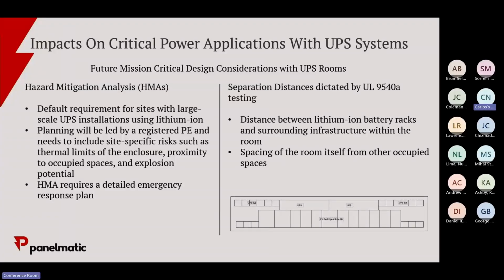I do think you're right - it's going to be a fire suppression person involved with that certification, because they'll have to show either that they're keeping the level below the 25% LFL threshold, or that they can move enough airflow in the room to basically clear it in under, I think, 2 minutes - don't quote me on that. But there's a designated time frame for how much air you have to recirculate in that confined space for it to be deemed sufficient and get the stamp of approval.